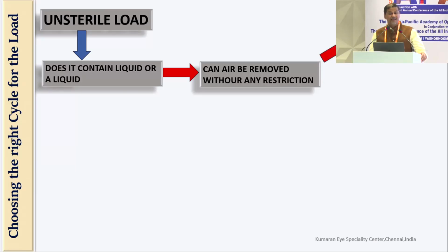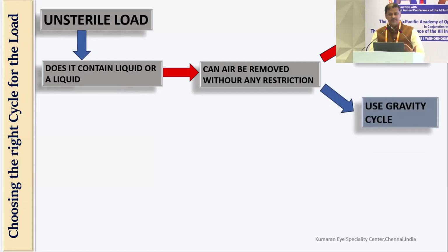And if the air cannot be removed from these instruments, for example, ophthalmic practice has a lot of hollow instruments, then use the pre-vacuum cycle, which is simply the class S or class B, which I told you. If the air can be removed easily, then use a gravity cycle. So the gravity or the vertical autoclave does have a role in ophthalmic practice if you're using it only to sterilize naked instruments and your linen. If you're using hollow instruments, please don't use the gravity cycle autoclave. The pre-vacuum cycle is enough.